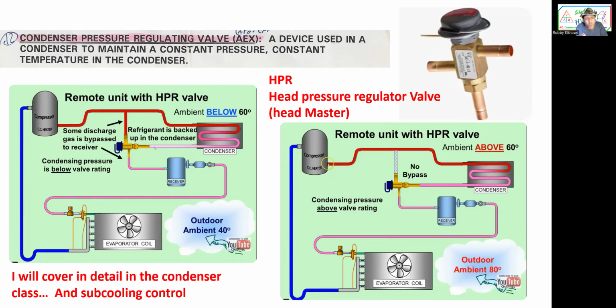So remote unit with HPR valve, some discharge gas is bypassed to the receiver. Why? Because ambient temperature is 40 degrees. On the other slide, you see remote ambient temperature above 60 degrees, no bypass. The one on the right side, outdoor temperature 80 degrees, is just a normal refrigeration system. Discharge to the condenser, out to the receiver. You can see by color, red, pink, and then low side. Over there, you see red, but some of the red is going down to the receiver. See that? To keep the pressure high. Because if the high pressure goes too low, the low pressure goes too low, nothing works.